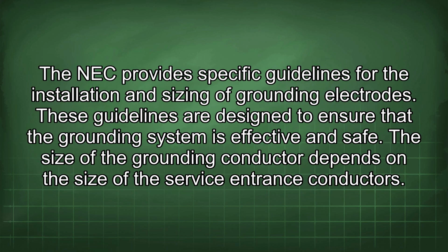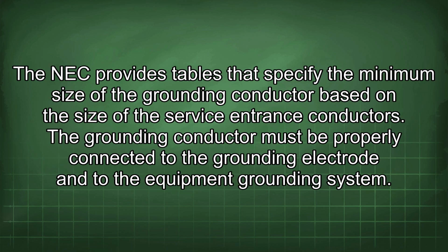The NEC provides specific guidelines for the installation and sizing of grounding electrodes. These guidelines are designed to ensure that the grounding system is effective and safe. The size of the grounding conductor depends on the size of the service entrance conductors. The NEC provides tables that specify the minimum size of the grounding conductor based on the size of the service entrance conductors. The grounding conductor must be properly connected to the grounding electrode and to the equipment grounding system.